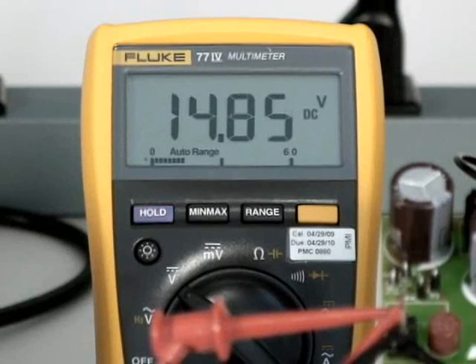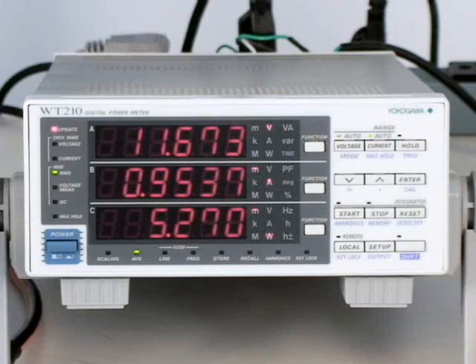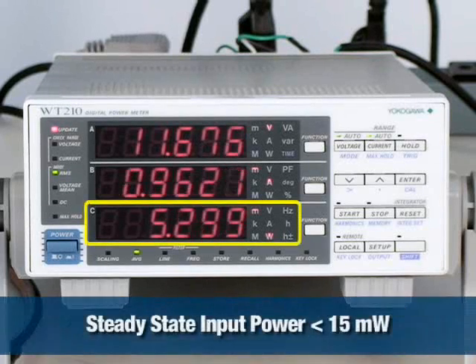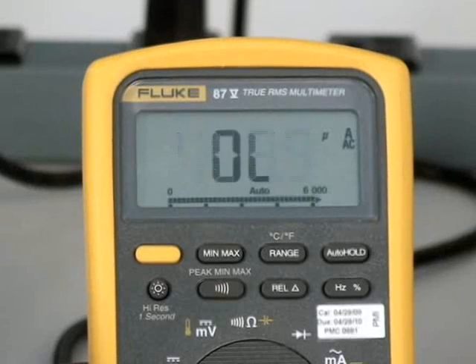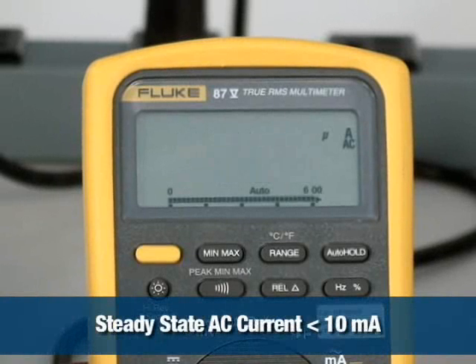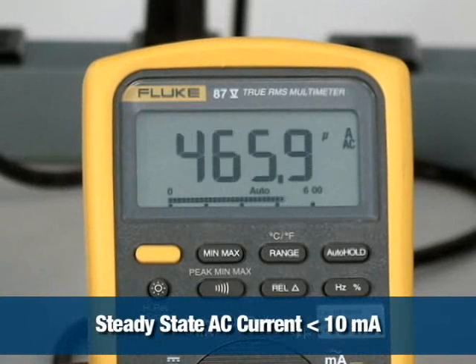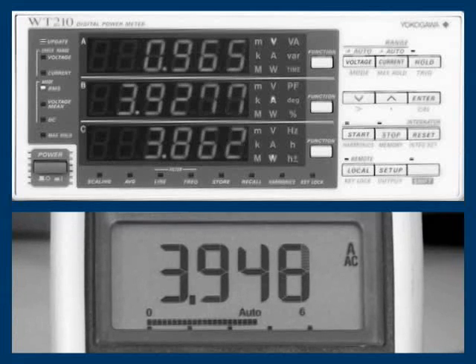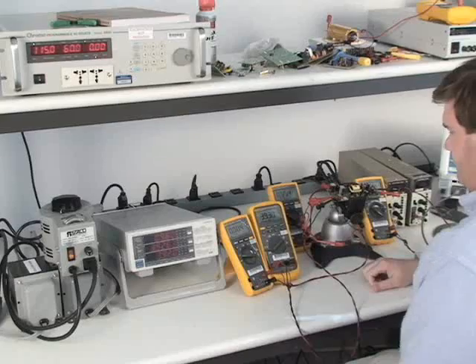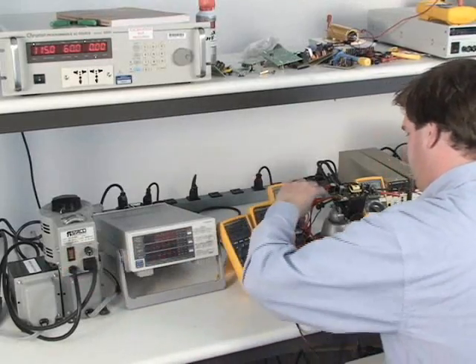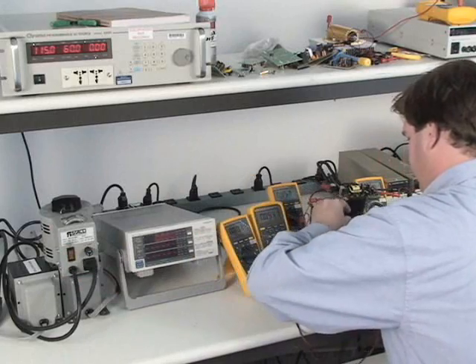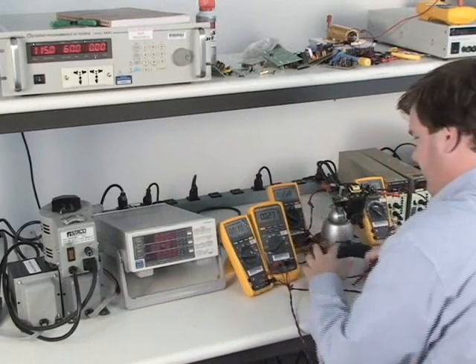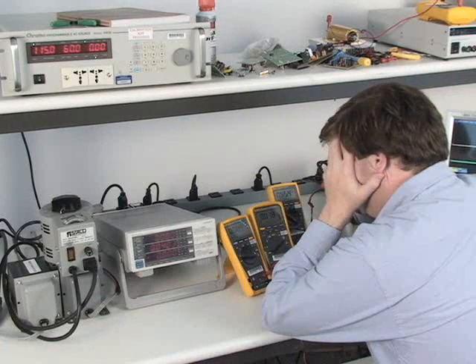You should also see the voltage on the DC bus increase as you apply the AC voltage. If you're using a wattmeter, the steady-state AC input power should be less than 15 milliwatts. And if you're using two multimeters instead, the steady-state AC current should read less than 10 milliamps. If you see an input power or AC current higher than this, then there is a fault on your board. Turn off the AC source and disconnect the AC input. Continuing to increase the AC voltage under these conditions may cause a destructive failure on your board.